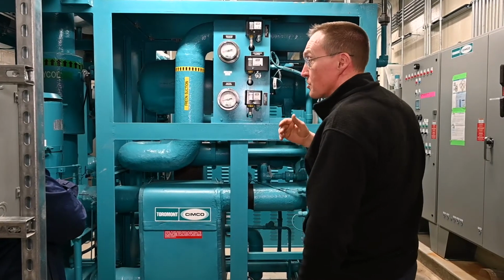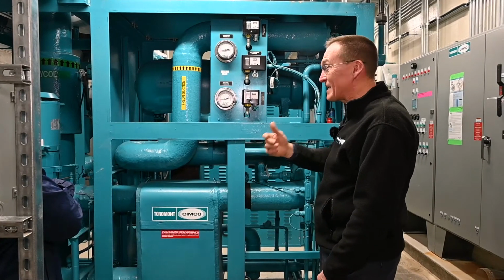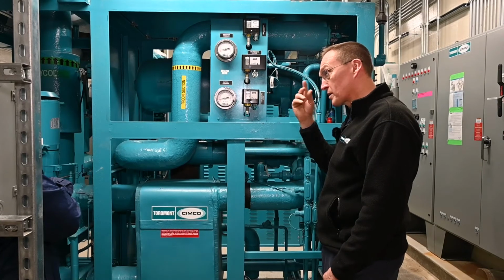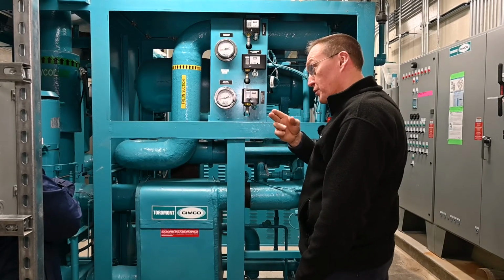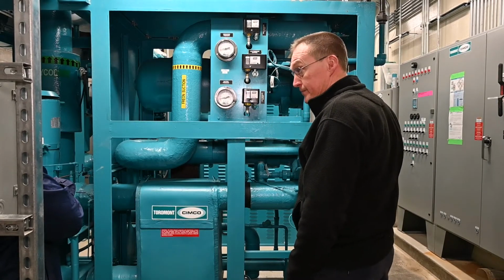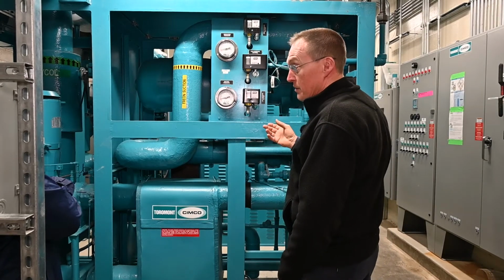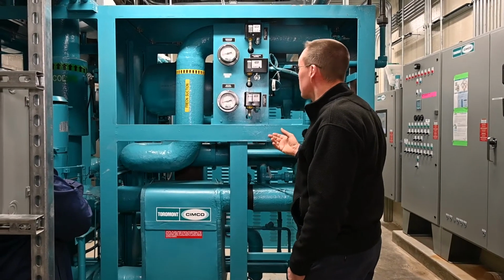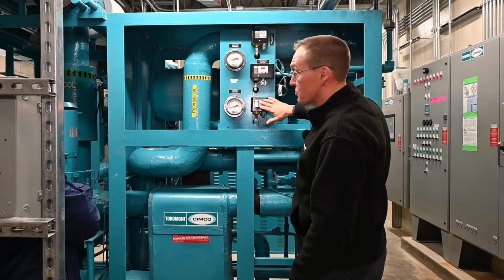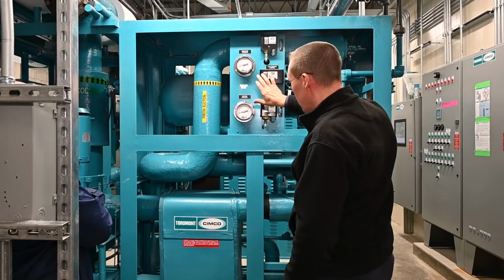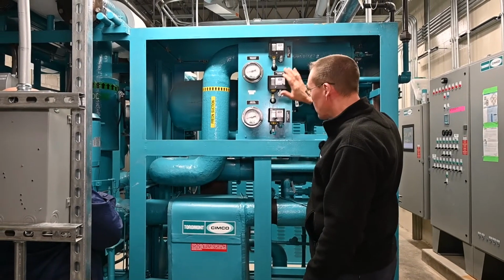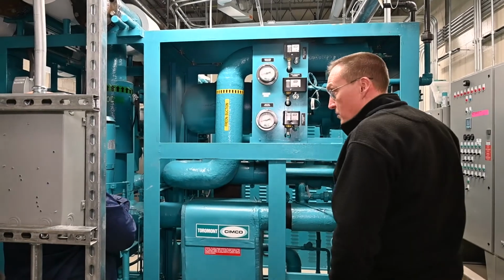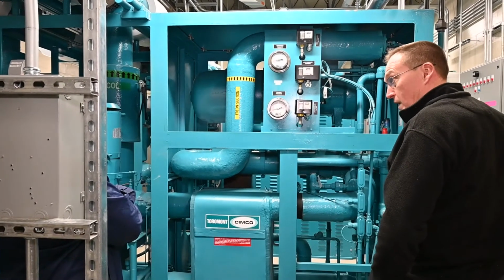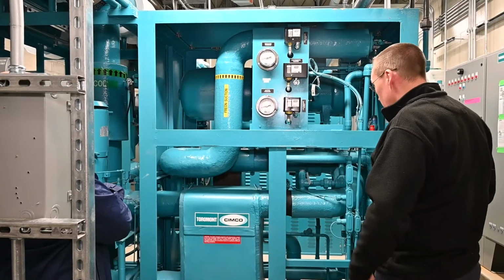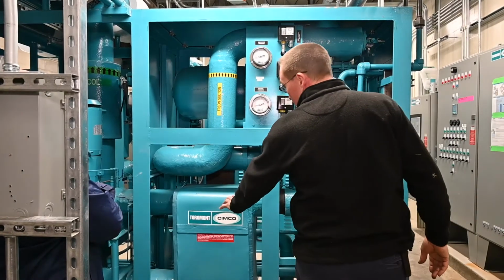We do that so that you get the most amount of heat that you can get out of that warm glycol loop, so you get your heat for your Zamboni water, okay? Which is going out there at about 100 degrees glycol temperature. All right? Then you have 3 safety controls here, which are hidden behind the panel, that you don't want anybody to touch. If there's a problem, you pick up the phone, you call your service provider, and we can remote it.